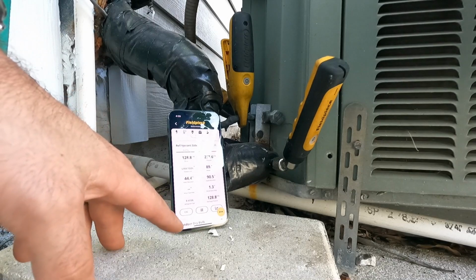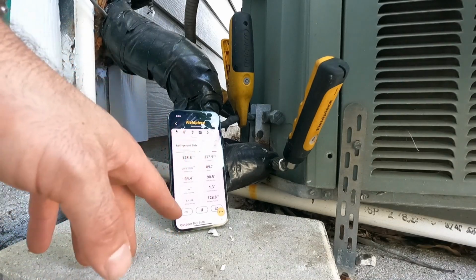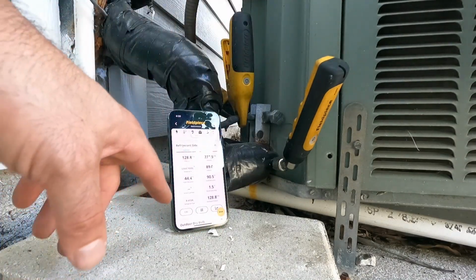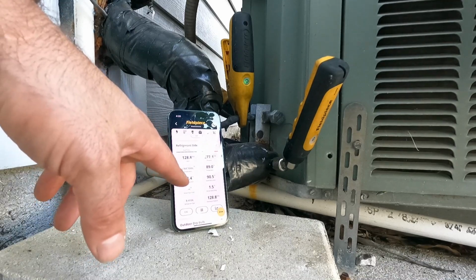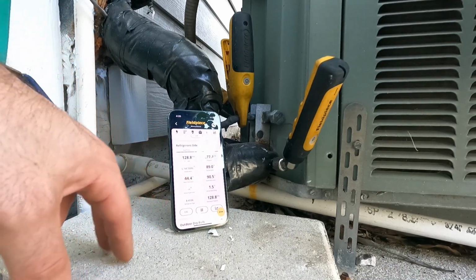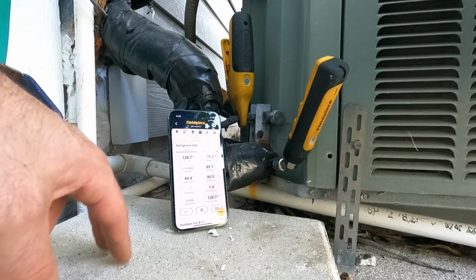So, 13-year-old unit, R410A. Subcool's not looking so hot, but we just got the thing operational. Probably got a high heat load inside too. I'm sure this coil is also very dirty. But our vapor saturation temperature is at 44 degrees, so that's looking pretty good.